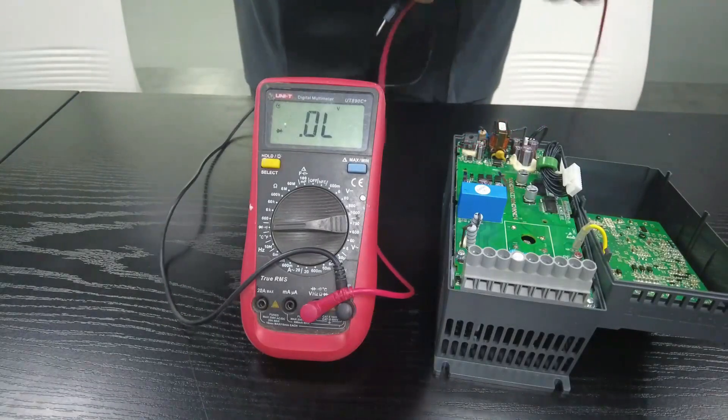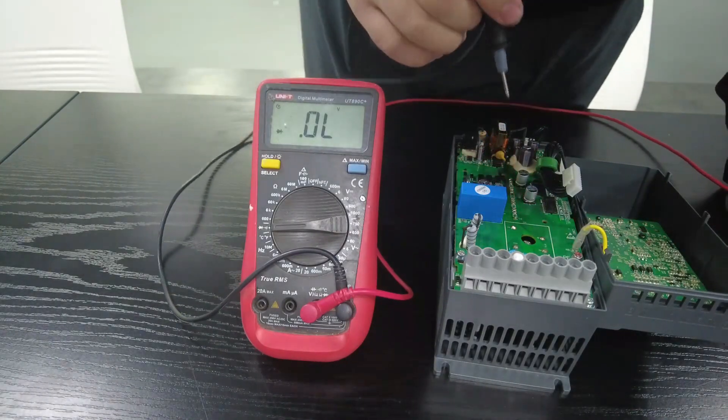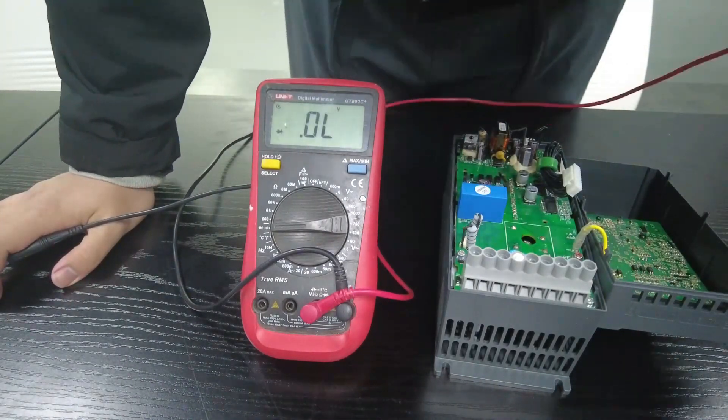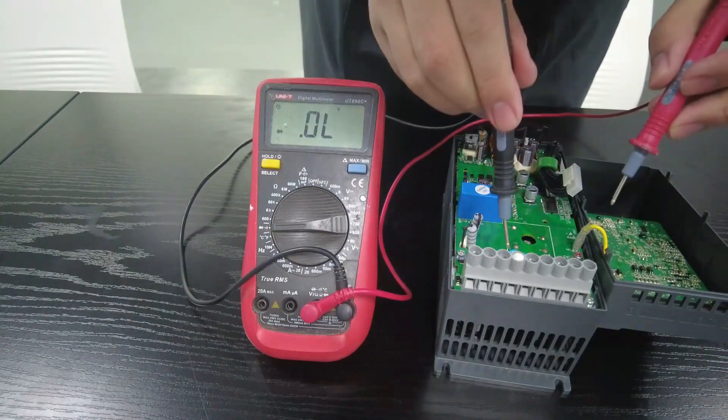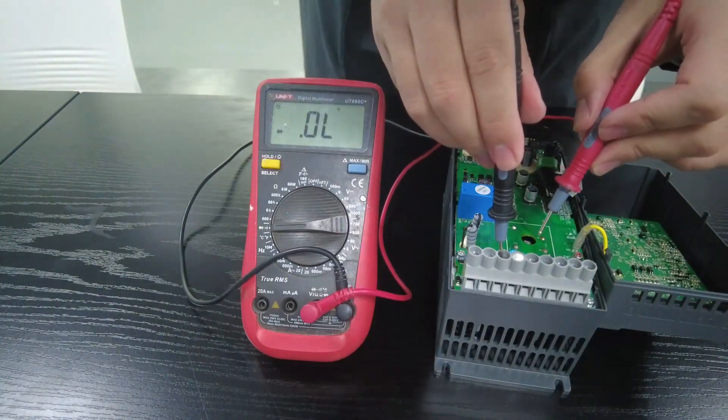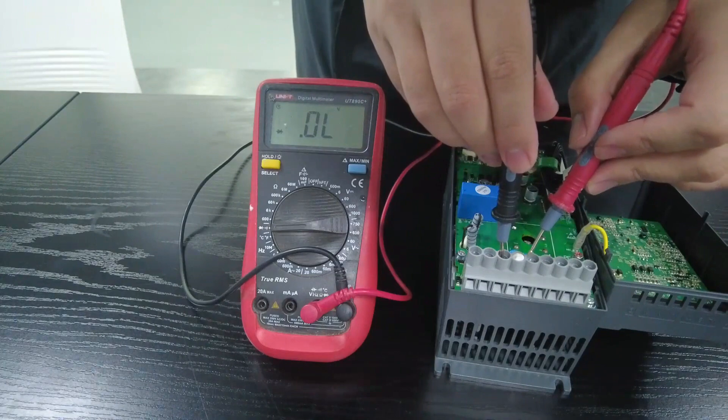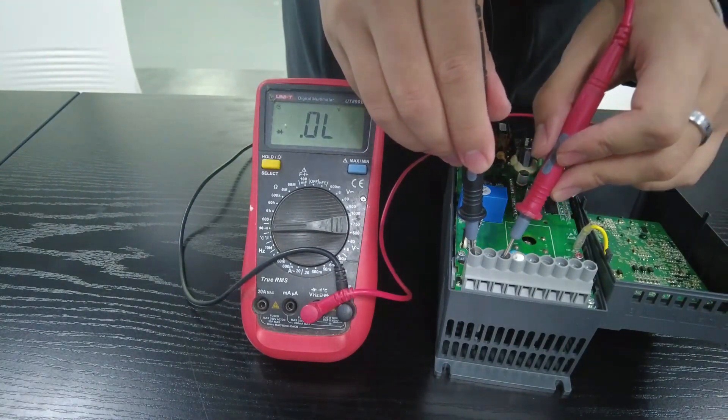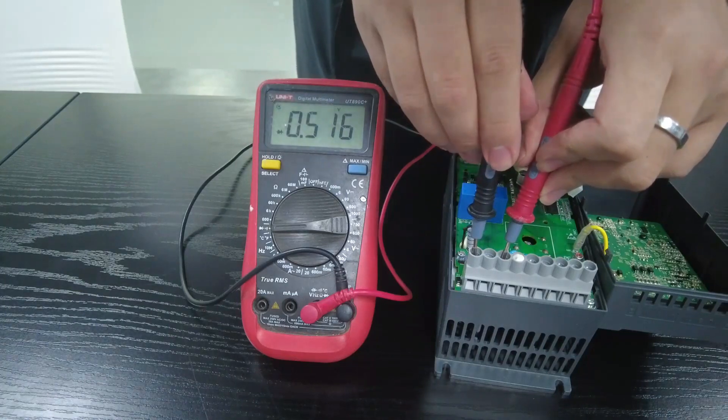Set the multimeter to the position of the diode. Connect the black test lead to the positive terminal and then use the red test lead to test the R, S, and T terminals in sequence. This is normal if the measured values are all around 0.5.